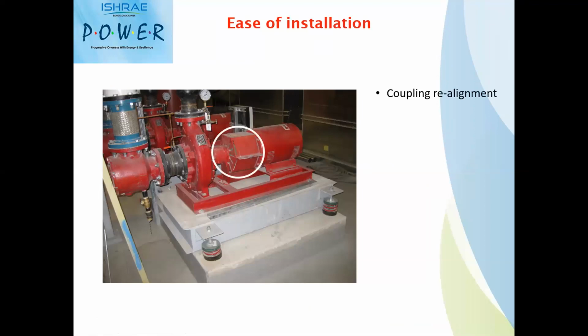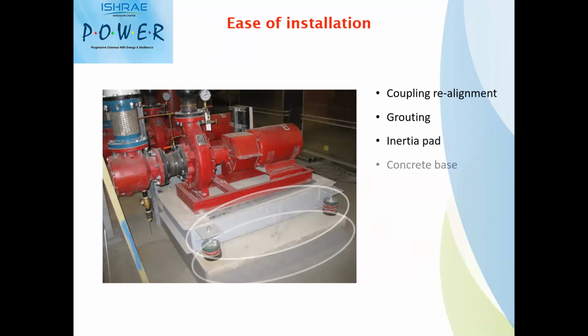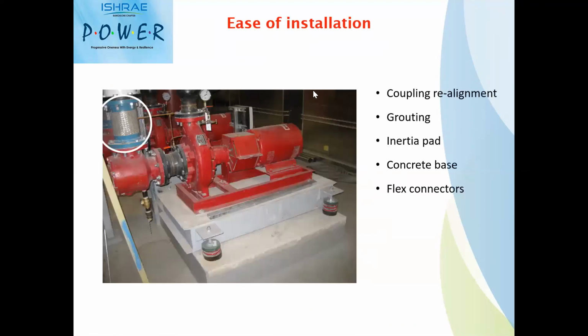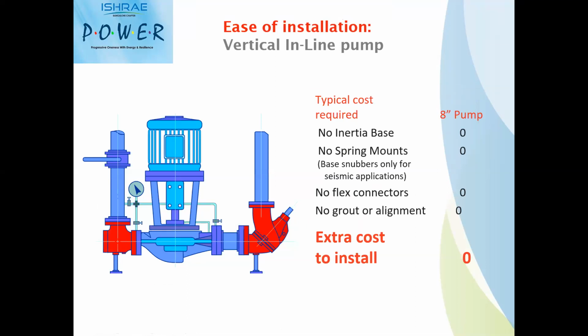And in terms of installation, which will be the easier pump? As I told you, you need to consider ease of installation also. End suction pumps require a base plate, a foundation, flexible bellows, inertia pads, and mounts to arrest the vibration. Overall, when you want to install these pumps, you need all these components. Whereas with vertical inline pumps, it depends on the manufacturer. Some vertical pumps may need support from the ground, some may not. But overall, vertical inline design requires very little installation effort and can easily be installed in the piping itself compared to end suction pumps.